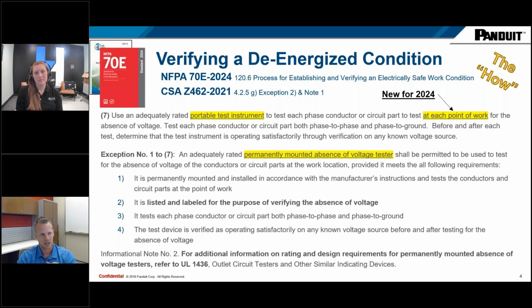Absence of voltage testers are no different. It's got to be listed and labeled for the purpose of verifying absence of voltage, and what that means is it's UL 1436, which is the UL standard for a bunch of other stuff too, but absence of voltage testers are in that standard, and it lays out what an absence of voltage tester needs to do, what tests it needs to accomplish and be tested to by UL to be called an absence of voltage tester. So there's a whole other standard around what this product needs to do.